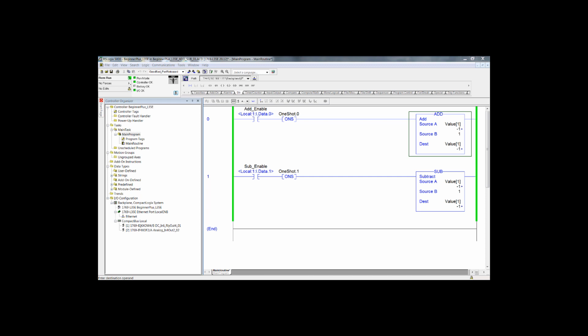What is the value? -1. We could have used unique memory locations for each of these math instructions. However, we wanted to demonstrate both the nature of the math instructions, that they are executed each scan, that the rung is true, and that any math instructions can operate against any single memory location. It is very common to stack math instructions that execute against one single memory location in one single program scan. And we'll demonstrate this off and on in this volume.